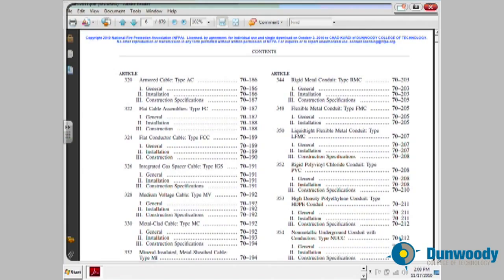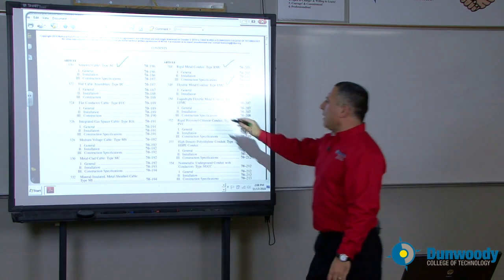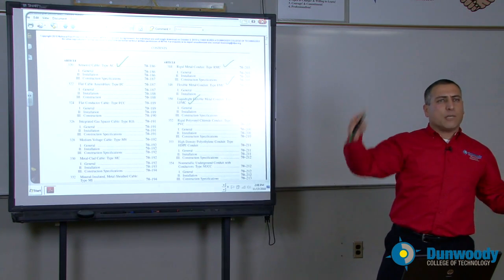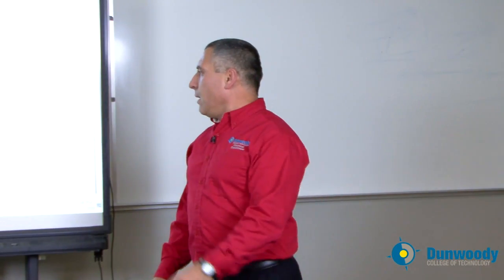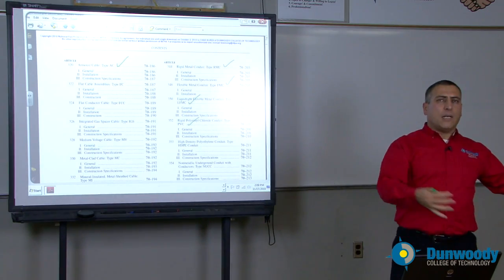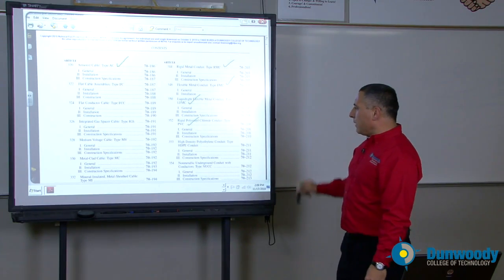Another very important wiring method is AC cable, rigid metal conduit — extremely important — and flexible metal conduit; you're going to use a lot of these. Liquid tight conduit is your conduit of choice for wiring equipment outside. If you're bringing underground cables to a building, PVC conduit will be your conduit of choice.